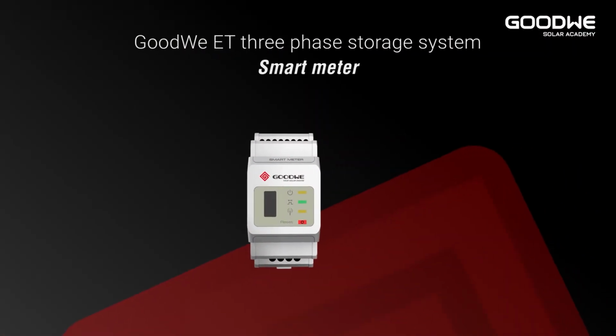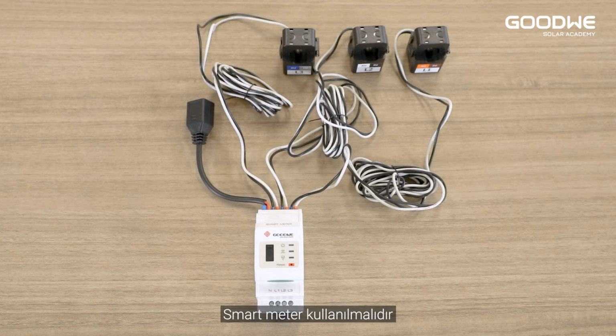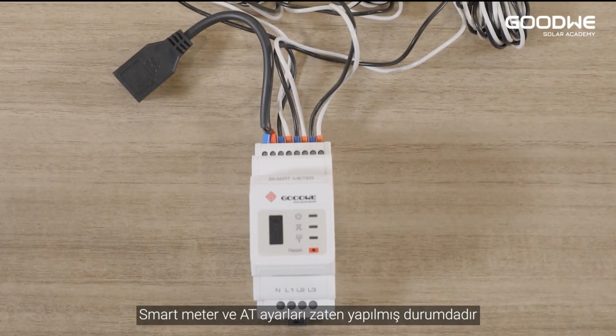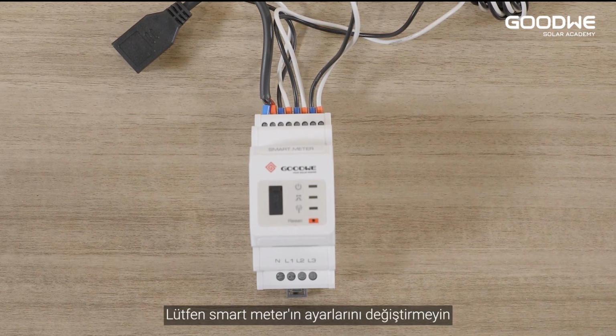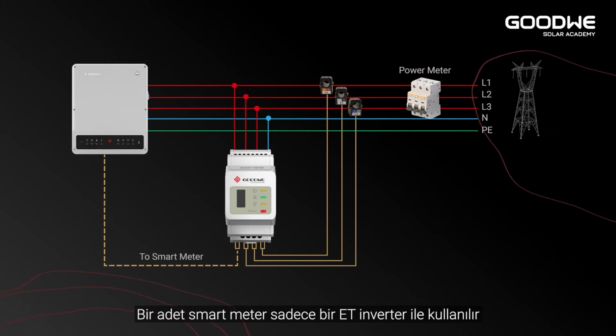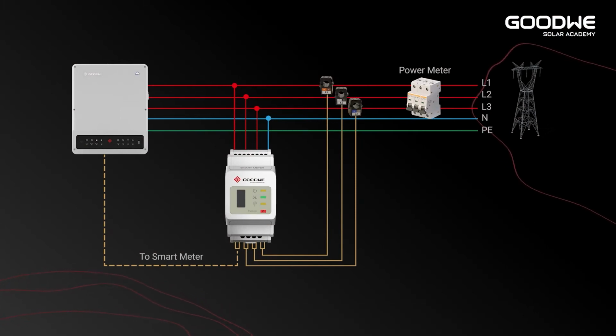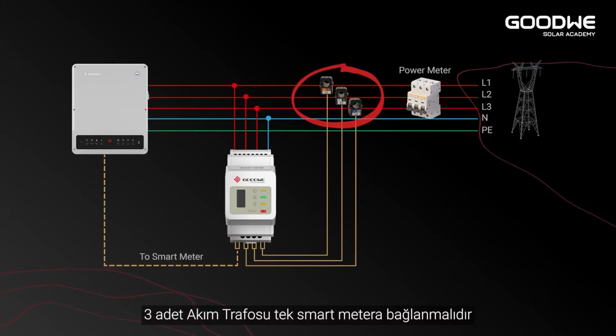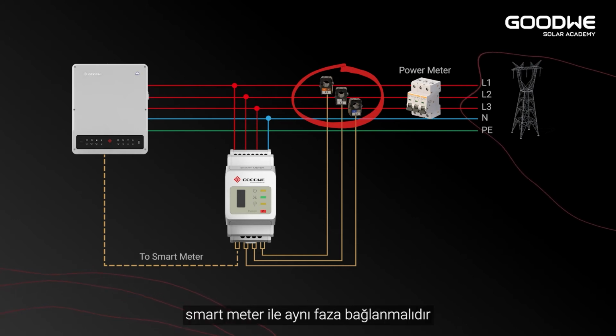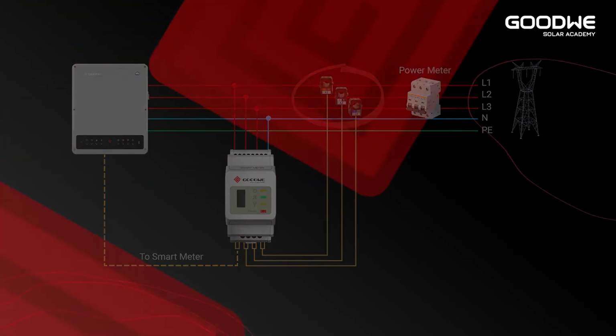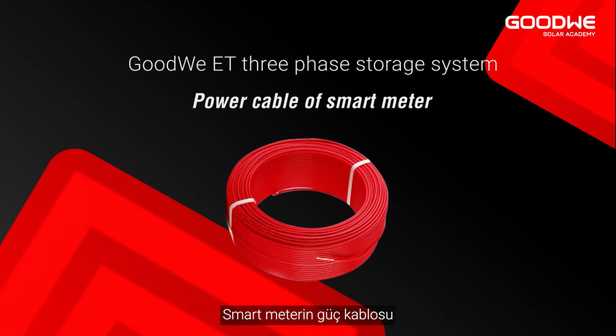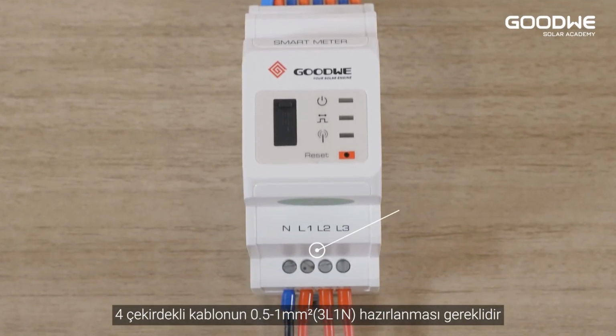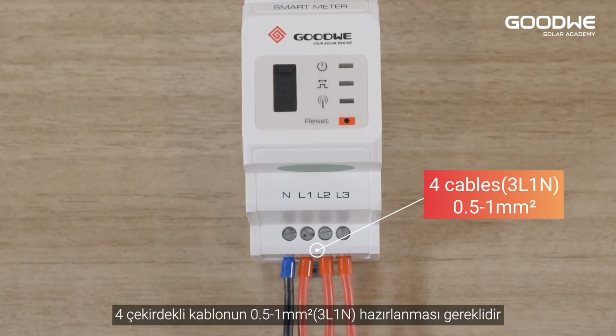Smart meter. This is necessary if the system does not have an additional energy management system device. The smart meter with CT is already configured. Please do not change any settings on the smart meter. One smart meter can be used with one ET inverter. 3 CTs must be used for one smart meter and must be connected on the same phase with the smart meter power cable. Power cable of smart meter. Installer should prepare 4 cables with standard 0.5 to 1 square millimeter.